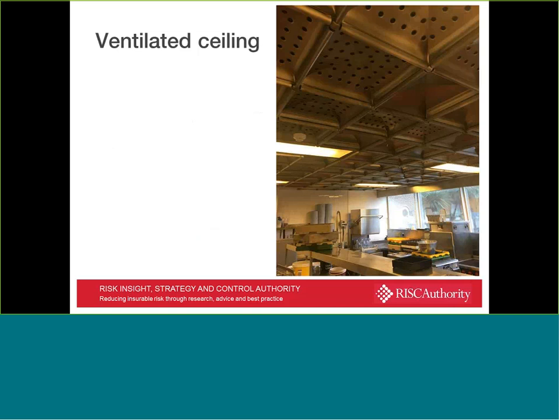But in terms of the ventilation systems, you don't always have simply a hood over the cooking equipment, you may have an entirely ventilated ceiling. These work in much the same way. They have intake and extract elements to them. They draw the heated air out with the grease particles mixed in, and they push cool air back in, and the grease is captured into the ceiling pods, which is a modular system, so you can remove the pods and clean the grease that way.